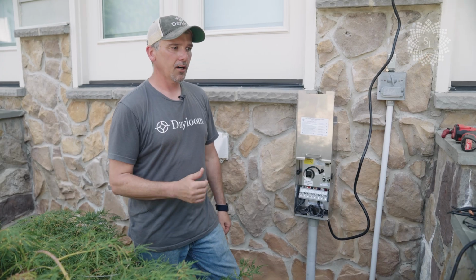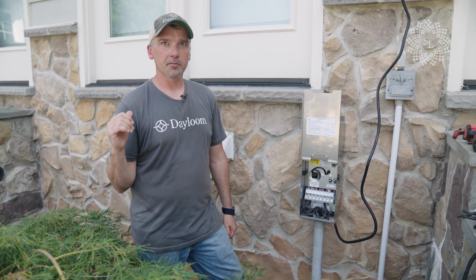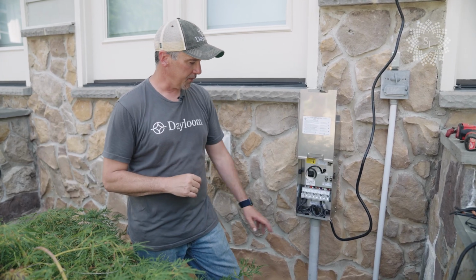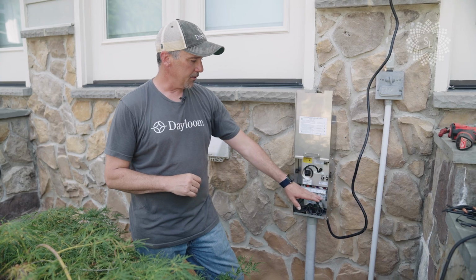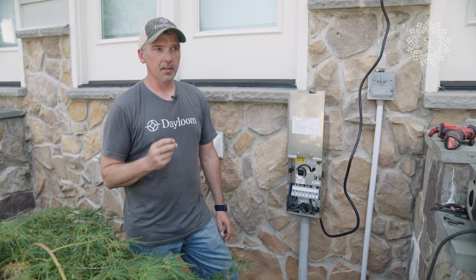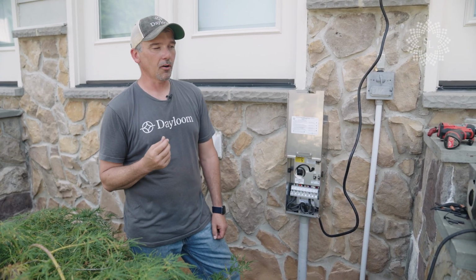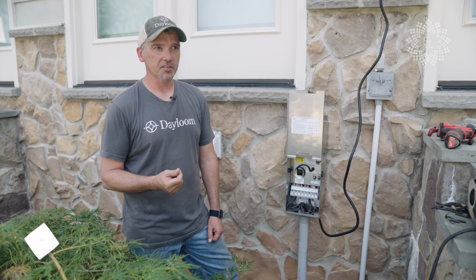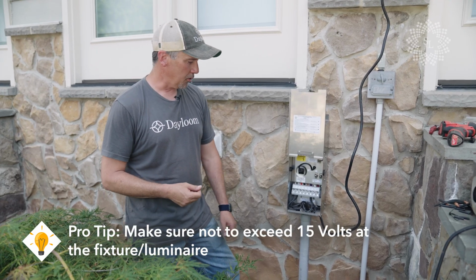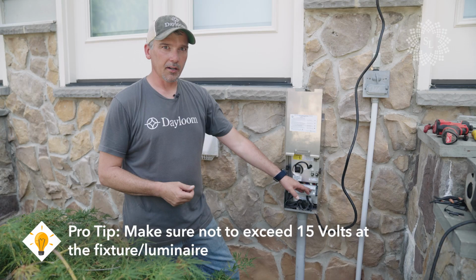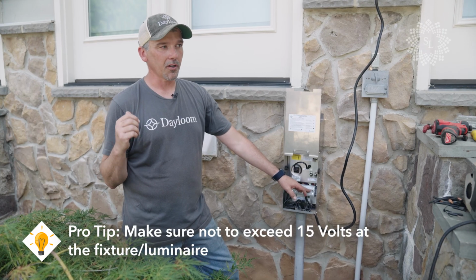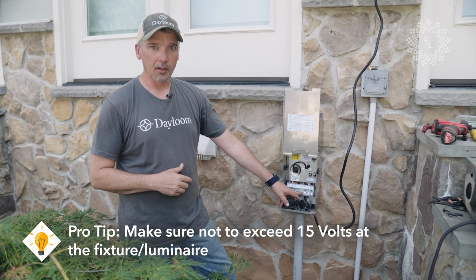So what I'm going to do now is take my meter and go test the voltage on these three lines. One important thing to keep in mind is you don't want to be over 15 volts at your fixtures. I'm at 18 right now. I'm expecting to be under 15, but if I'm over, I'll come back up and bump it down.